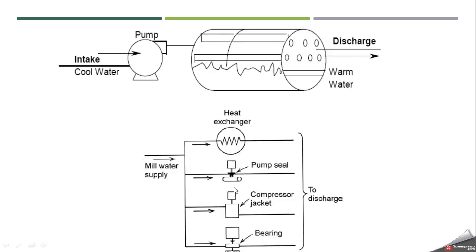This is a schematic diagram of a once-through system. Cold water is taken from a source using a pump and sent to a heat exchanger or heat transfer surfaces. After absorbing the heat, the water is discharged on the other side. In another configuration, the water supply is divided for cooling different parts like heat exchangers, pump seals, compressor jackets, and bearings, and then discharged without recycling.